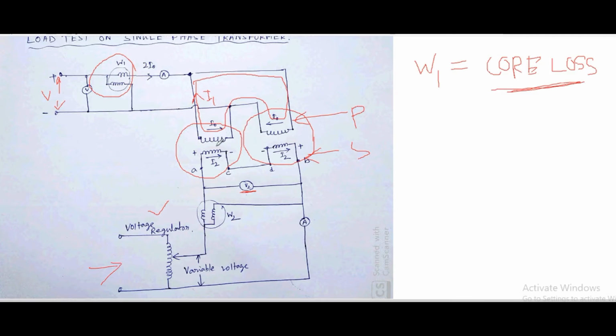That means the copper loss of these two windings is supplied by this voltage regulator, and this wattmeter W2 will read this copper loss. So the W2 wattmeter will read the copper loss, that is the I squared R loss. So it will give the copper loss.